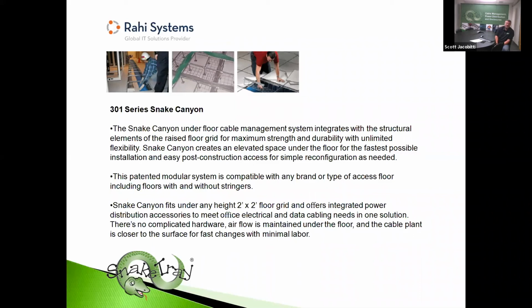We're looking at anywhere from 20 to 30 seconds per 2-foot basket, so ease of installation and the ability to do MAC work is very, very simple. These cable trays are volumetrically large, so we can handle 2,000 to 3,000 cables in any of these baskets. They're available anywhere from 2 to 12 inches in depth, so there are lots of different possibilities for running our low voltage cables below that raised floor.